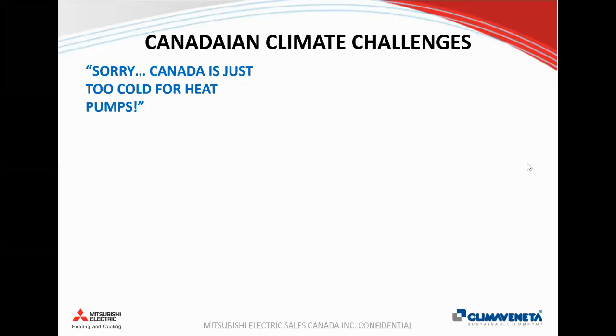Well, one of the limitations that I touched on and hinted at is the ambient temperature limitations, which we'll talk about in a little bit. For right now, I'll just say the cutout for the technology that is available from Mitsubishi Electric typically cuts out at minus 15 degrees Celsius or 5 degrees Fahrenheit. So typically when someone's considering an air-to-water heat pump, that's usually the first question: what's the coldest temperature I can run the heat pump? And when I say that temperature is minus 15, usually they say, oh, sorry, our design temperature in Toronto is minus 23, so it looks like we can't use your heat pump.